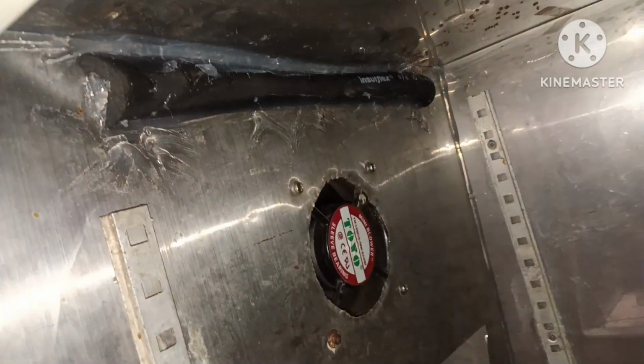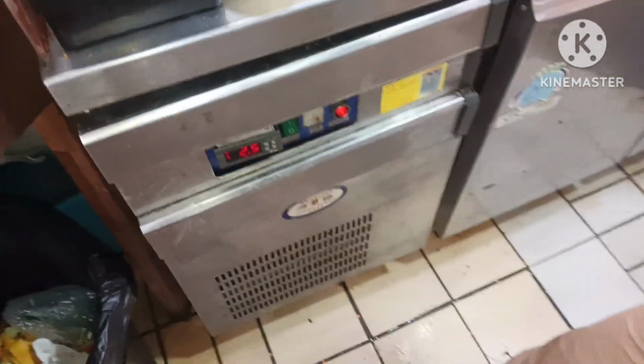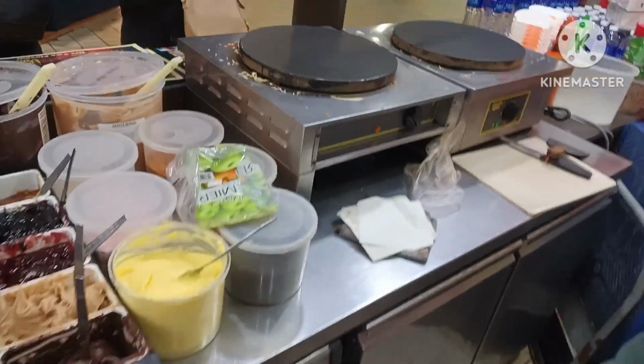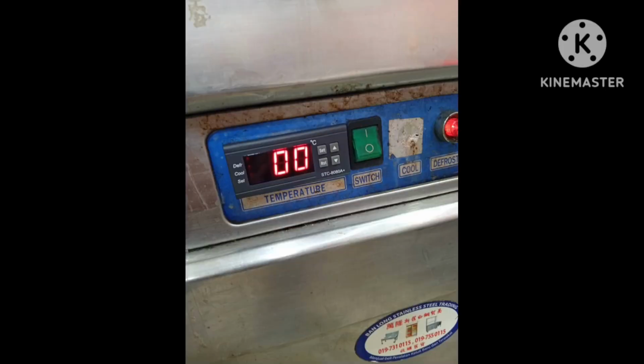The water will dry automatically from there. So I have cleaned it. There was also a lot of ice in the cooling coil because the temperature meter had spoiled, that's why it wasn't cooling. So I changed the temperature meter, and alhamdulillah, it is okay now.